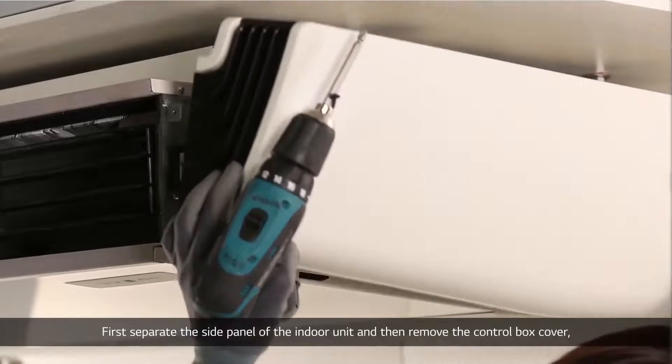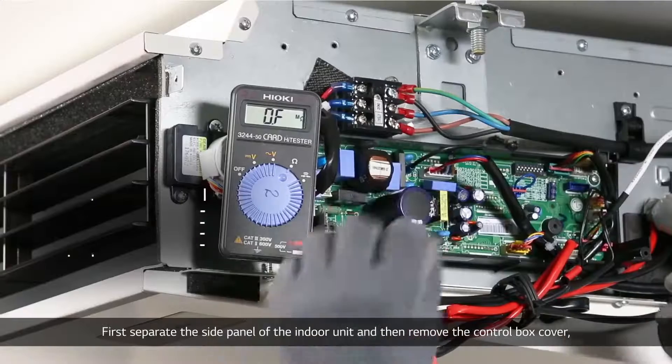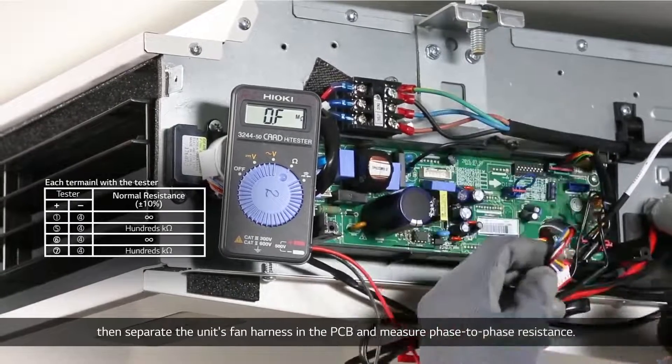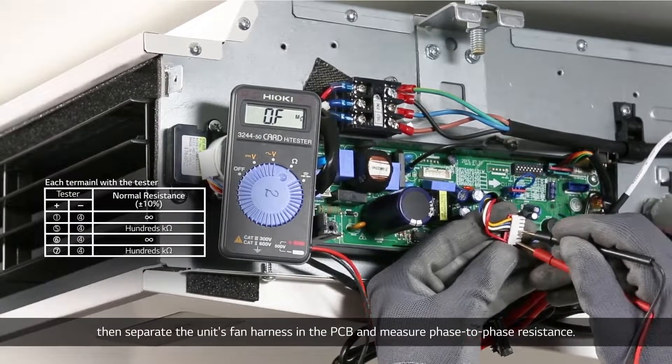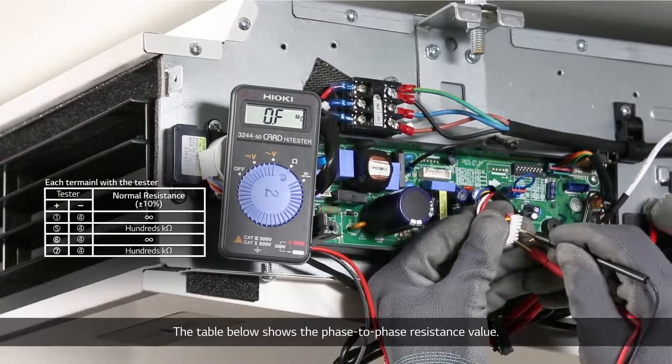Separate the side panel of the indoor unit, then remove the control box cover. Separate the unit's fan harness from the PCB and measure the phase-to-phase resistance. The table below shows the expected phase-to-phase resistance values.